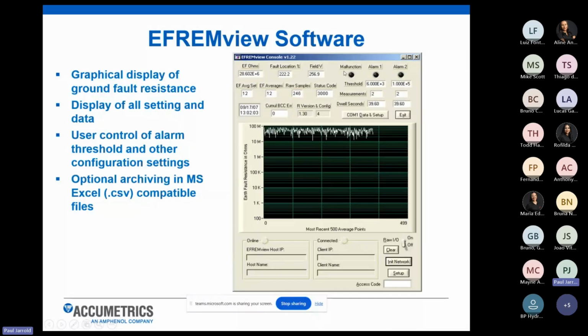It also has the ability to detect a malfunction alarm in the software, and we provide the field voltage, resistance values, and location factor, which defaults to 222.2 when there is no fault, and then the field voltage value of the machine. There are some other details in here that we don't need to go into in great detail, but essentially some more troubleshooting ability is in the software information that we provide. All of our users don't use the EFREMview software to monitor their equipment long term. This is mainly used in setting up and commissioning of the system.